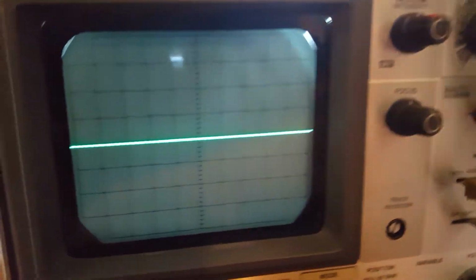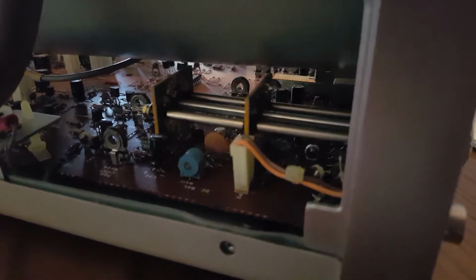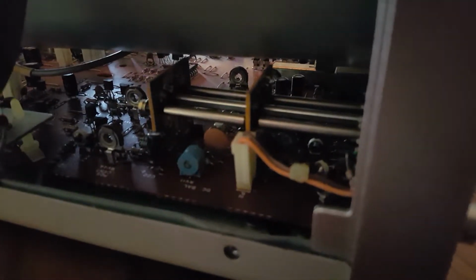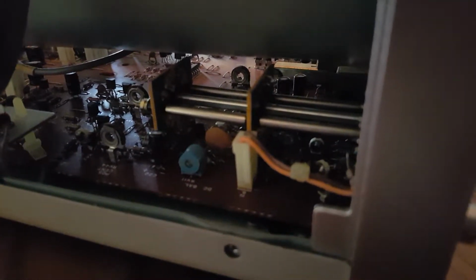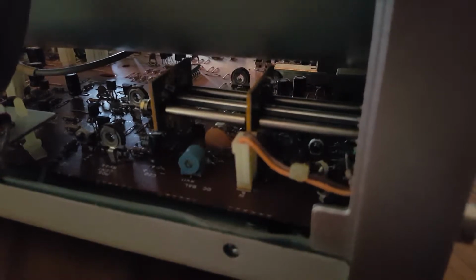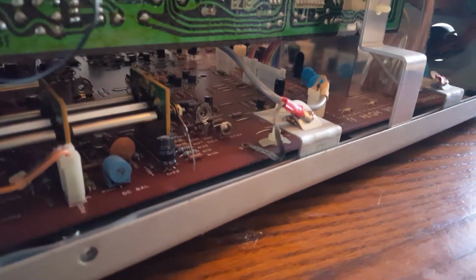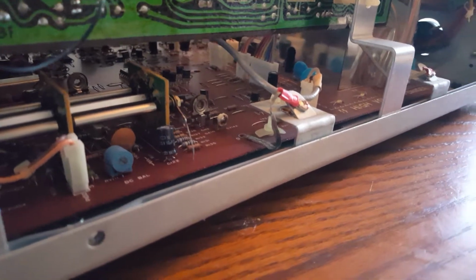If you want to adjust channel 1, you have to go inside the machine. That little blue pot right there, which is R11, is used for adjusting the balance volts per division for channel 1. And if you go to the other side, that little blue one right there, which is R111, is for adjusting channel 2.